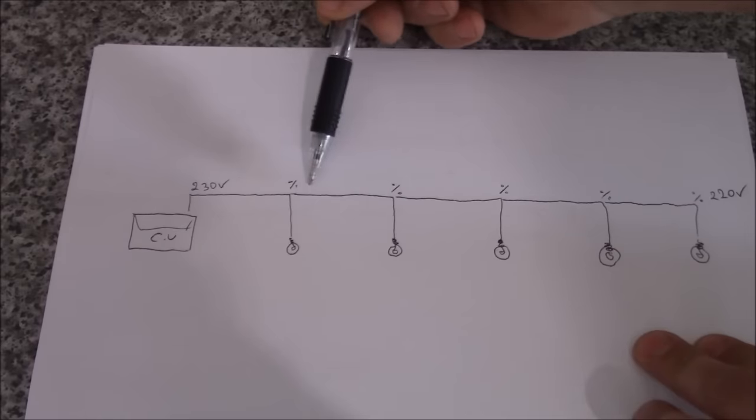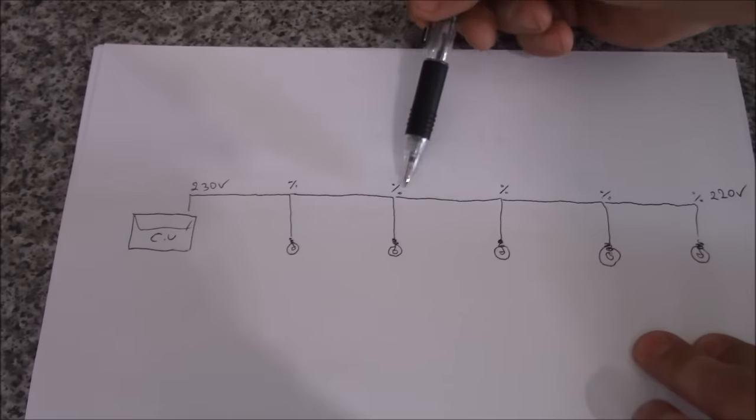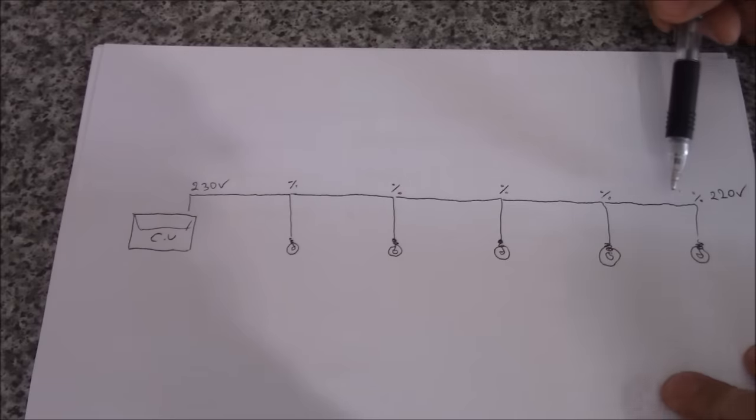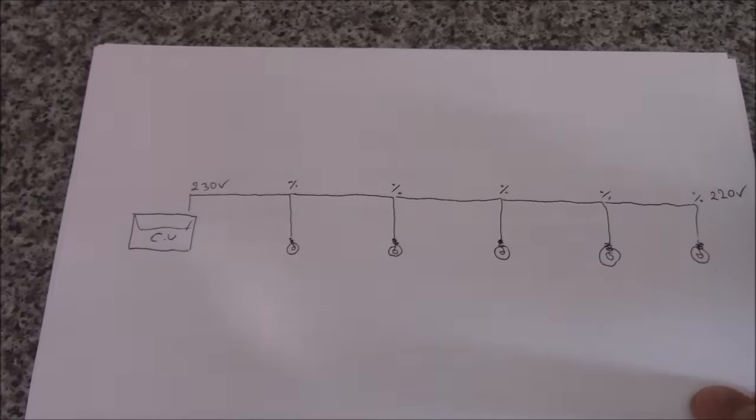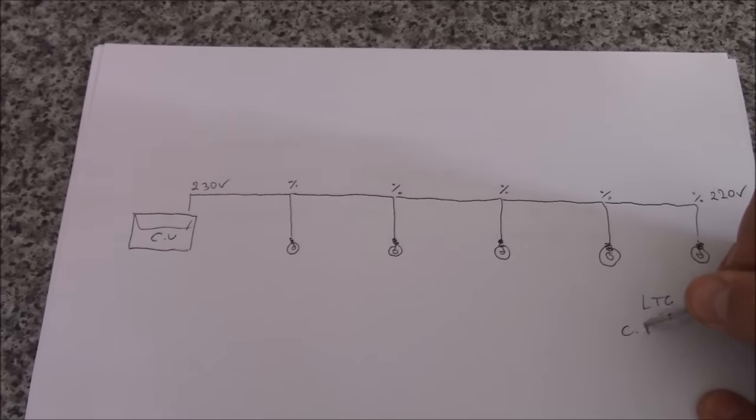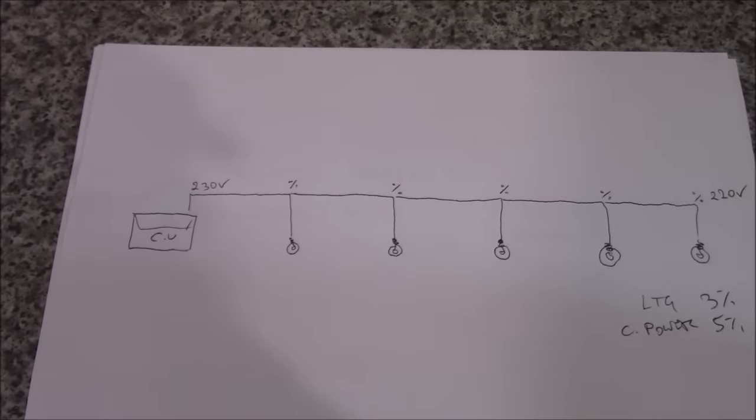At the beginning we've got 230 volts. So there's voltage loss in every let's say meter of the cable. So at the end it might appear that we've got the voltage only 220 volts. So in UK the allowable voltage drop for lighting circuits is 3% and for the general power is 5%.